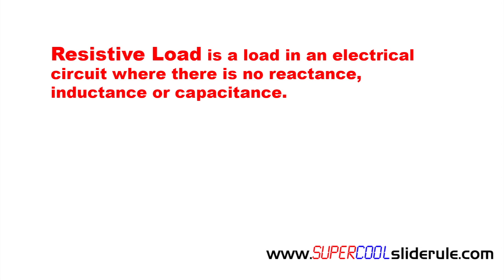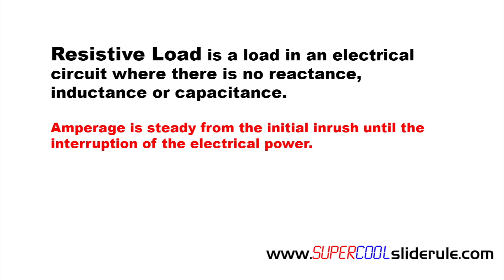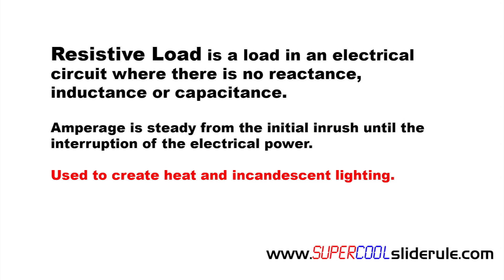It is purely resistive. The characteristics are the amperage is steady from the initial inrush until the interruption of the electrical power. Resistive loads have no capacitors and there are no starting devices or windings. Resistive loads are used to create heat and incandescent lighting.